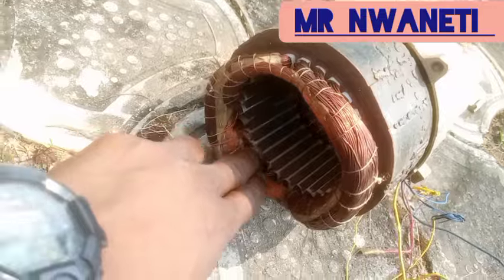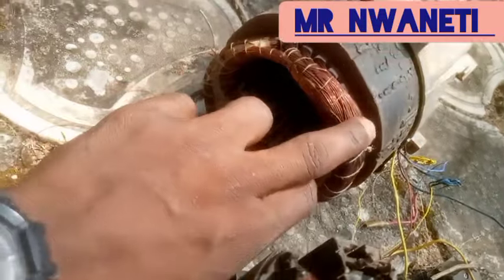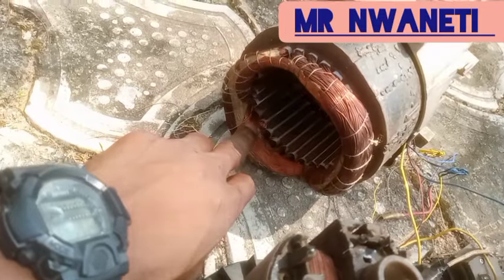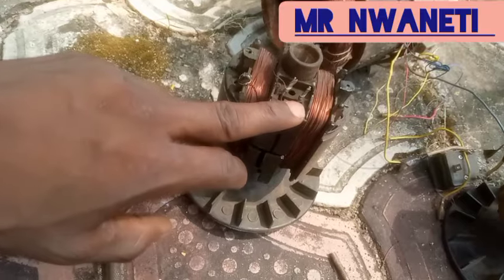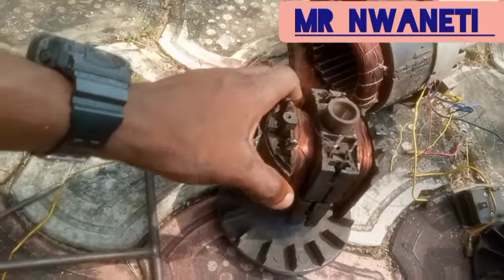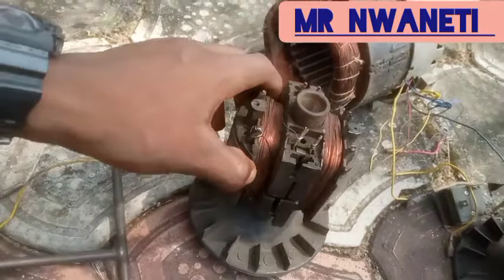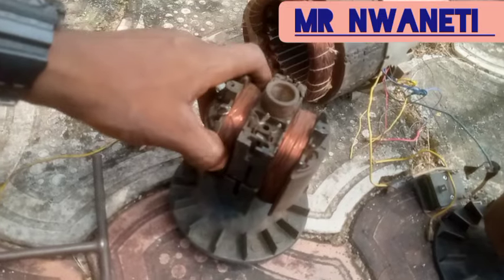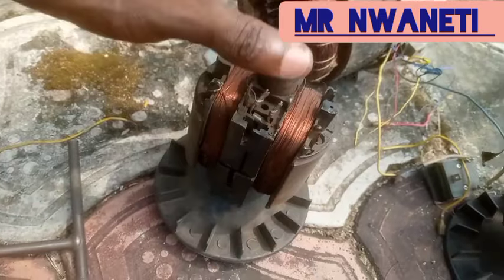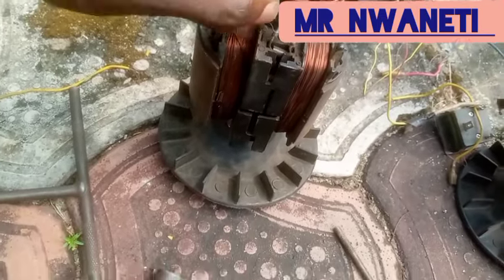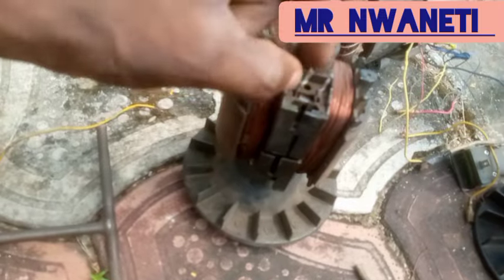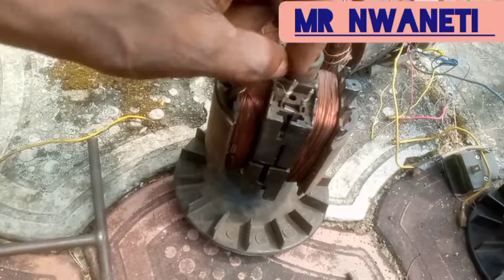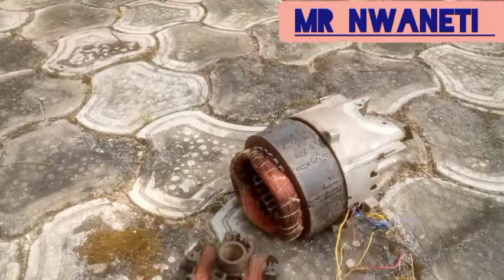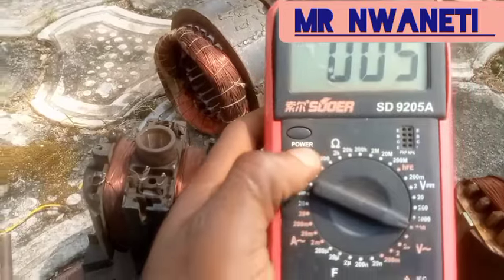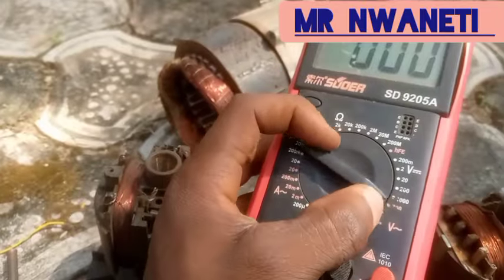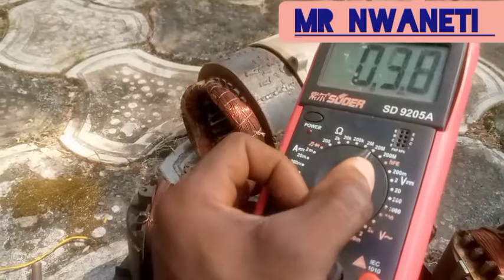All you have to do is check the winding, check the main coil, check the exciter, check the rotor, and physically inspect the winding to know if it has burnt out. Then check if the diode is short circuit, because most diode issues won't be physically displayed. All you have to do is get your meter, like this is my meter now, then switch it to continuity reading.